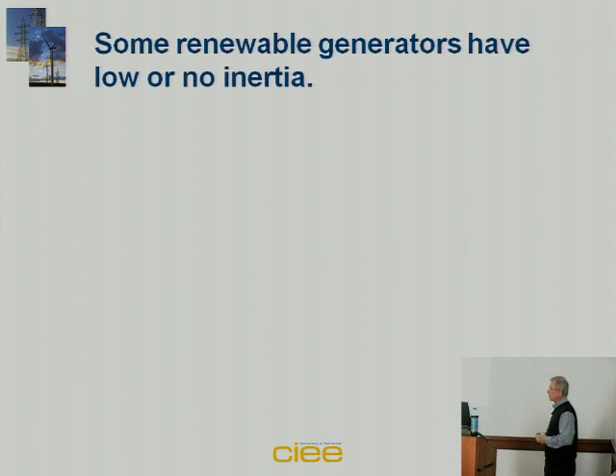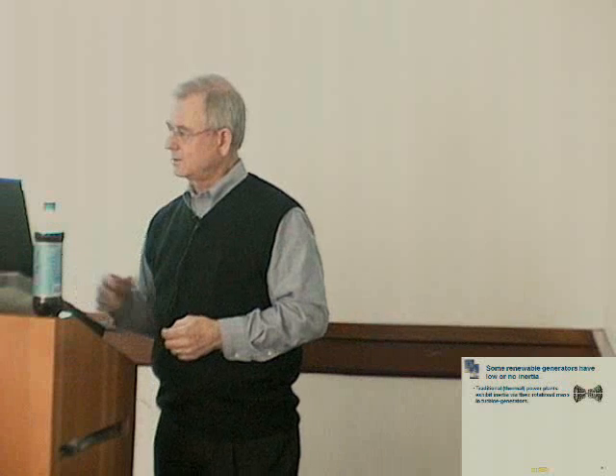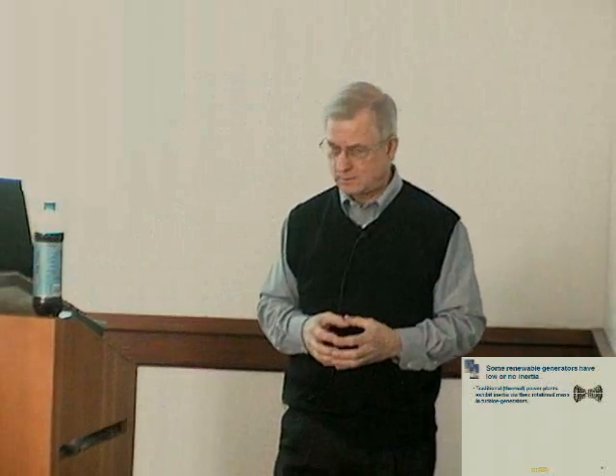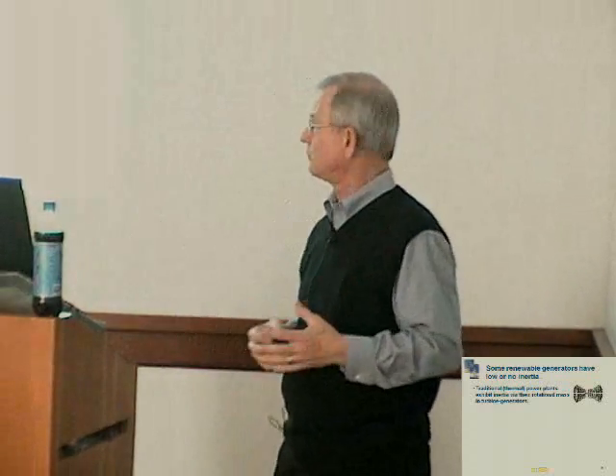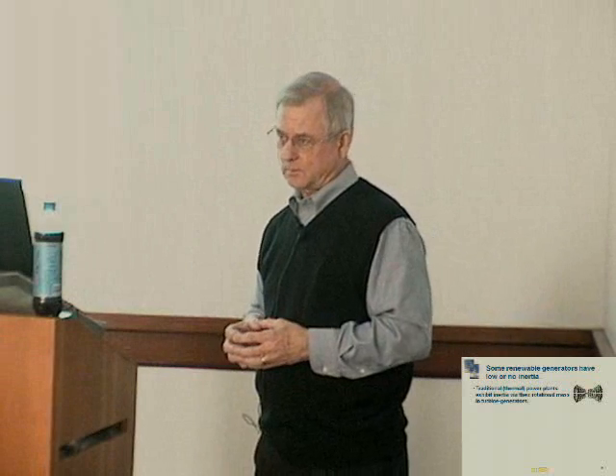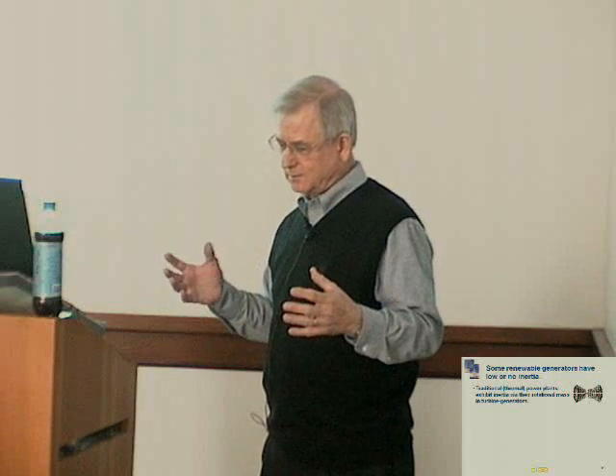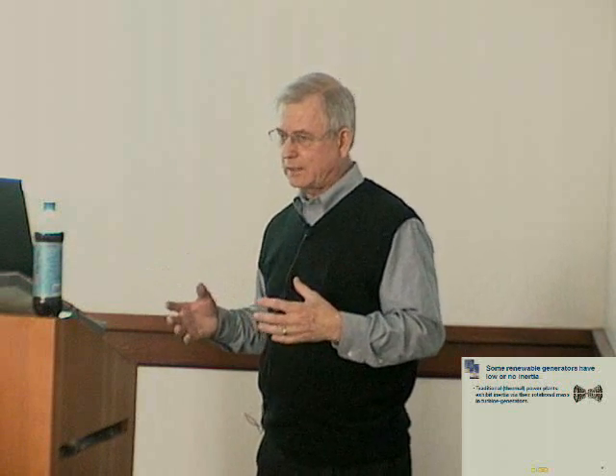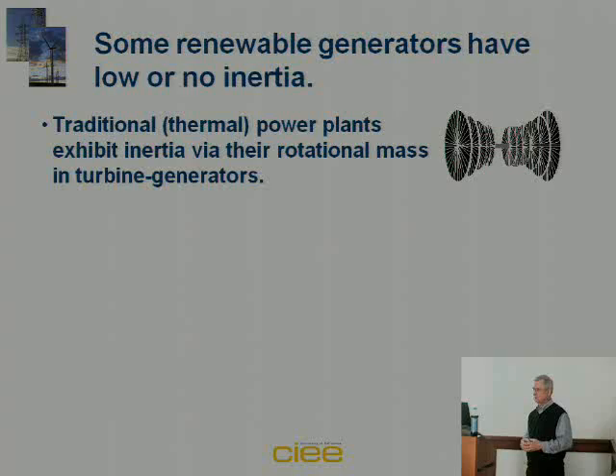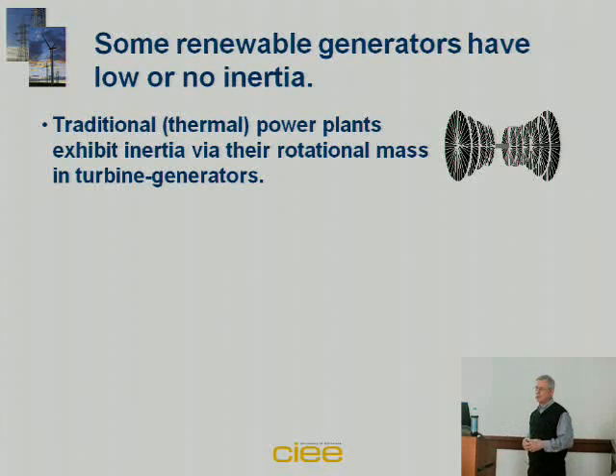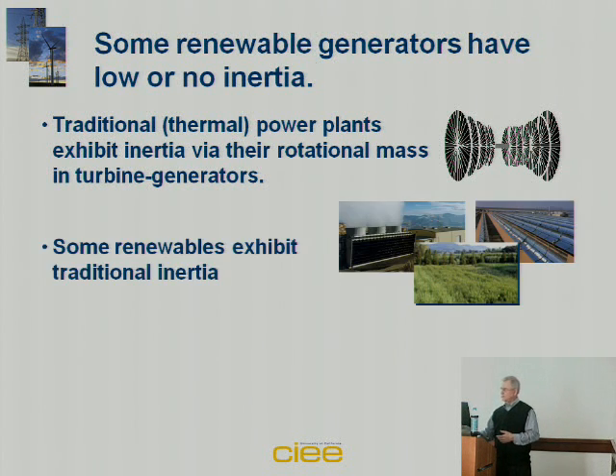Some renewable generators have low or no inertia. Traditional thermal power plants exhibit inertia via the rotational mass in their turbine generators. In a sense it's neither good nor bad, other than that this is what the system was designed for—it's what the operators are used to. So when a plant trips off, it doesn't immediately lose all the power; it tends to coast down, and operators are used to that. But now we're getting new power plants that don't necessarily do that.